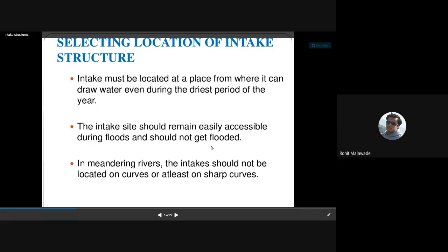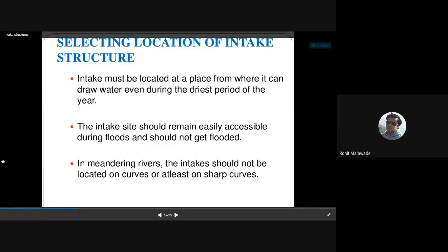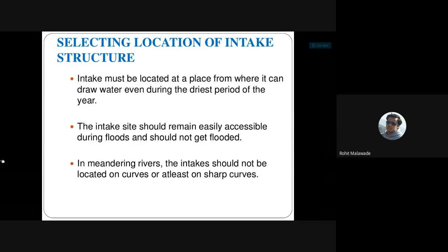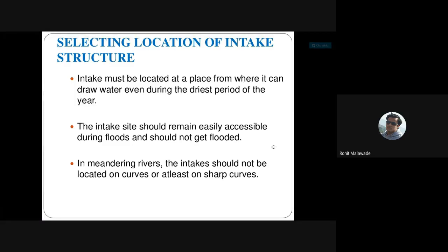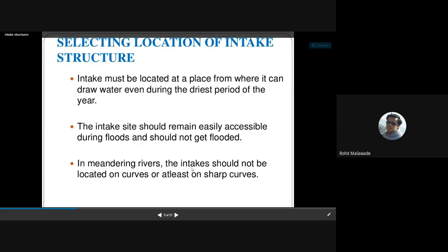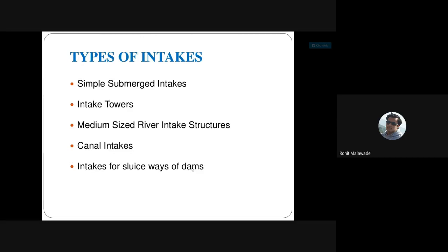The intake site should remain easily accessible during floods and should not get flooded. During the rainy season the source fills with water, and the intake structure should not get submerged, because if pumps are affected by flooding, the downstream site requiring water will also be affected. The intake structure should never be located in a flood-prone zone, and it should not be located at sharp curves of the river.